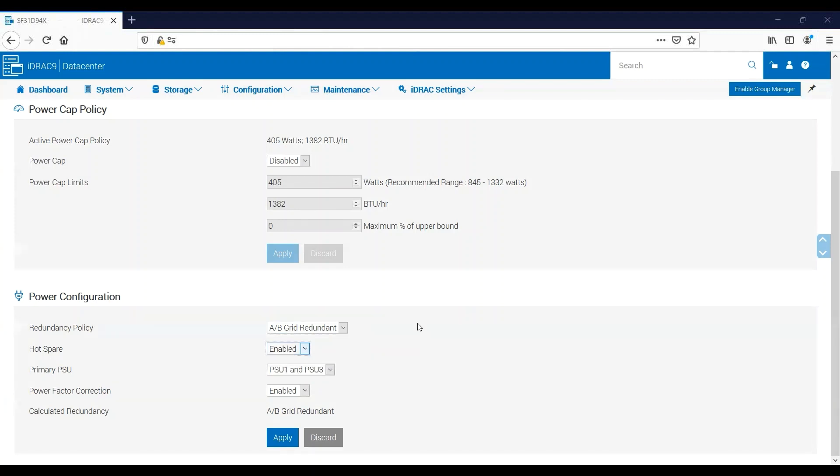While power supply one, or the active power supply, supplies all of the power needs to that server. So if the server only needs 100 watts of power, power supply one will supply all 100 watts, and power supply two will not supply any and will sit in the hibernating state. If the hot spare feature is disabled, then both power supply one and power supply two will each contribute 50 watts of power to the server.